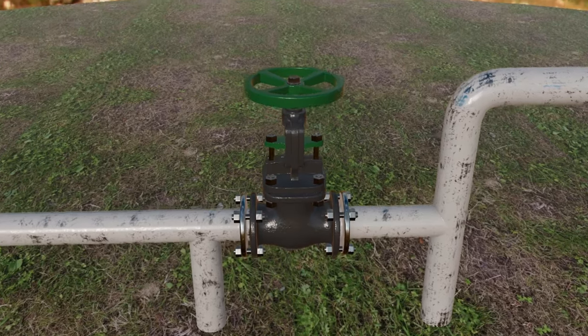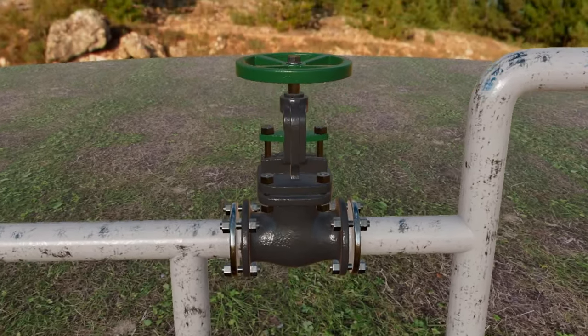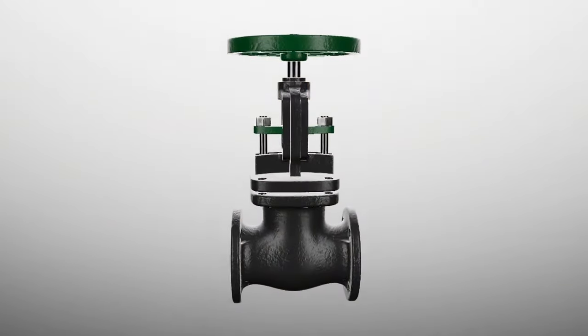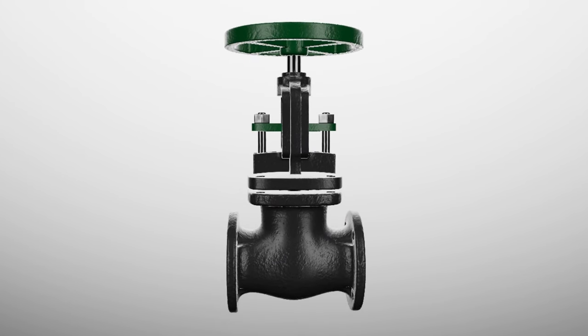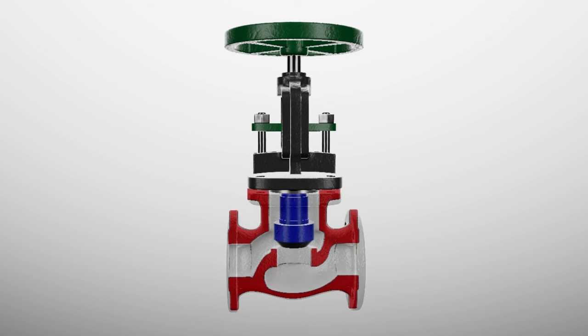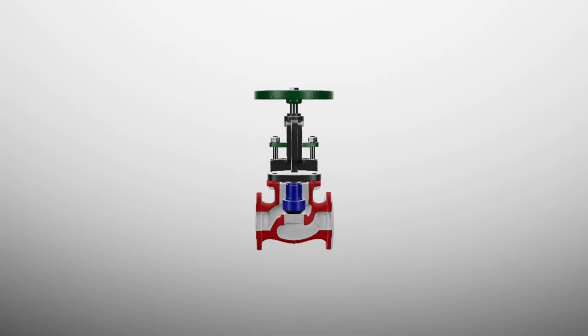This is a globe valve. The globe valve gets its name from the round shape of its external body. Unlike gate valves, it is not only used to stop and start the flow of gas and liquid, but also to regulate the rate of flow passing through it. This particular valve is manually controlled on-site by an operator. Globe valves can also be operated remotely via a pneumatic control valve.